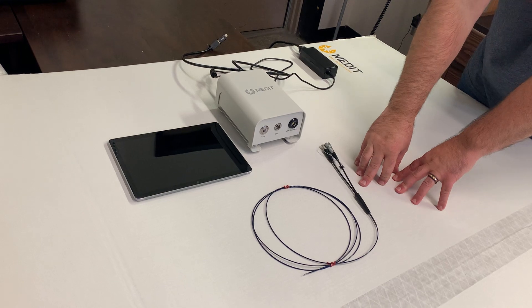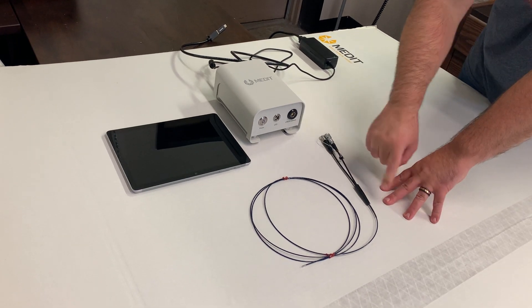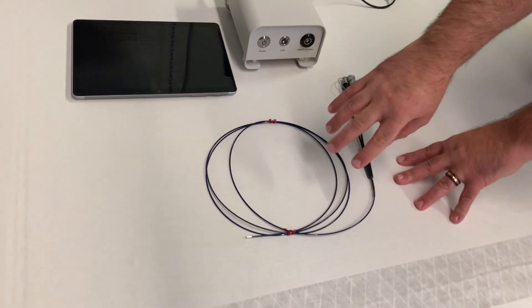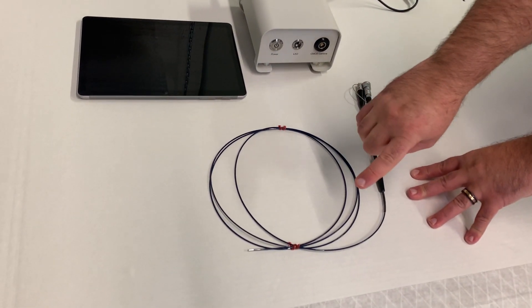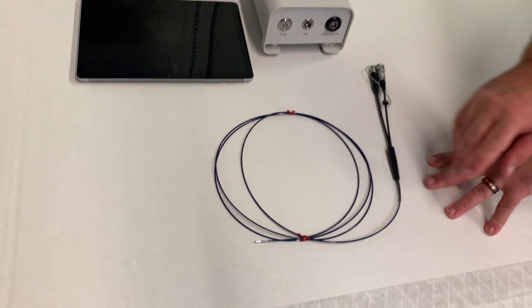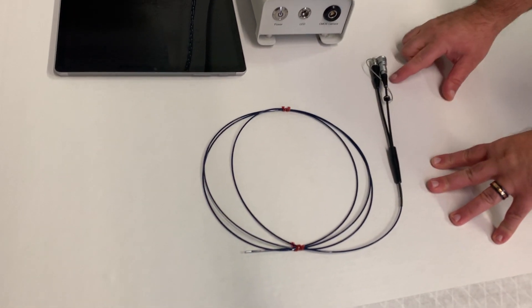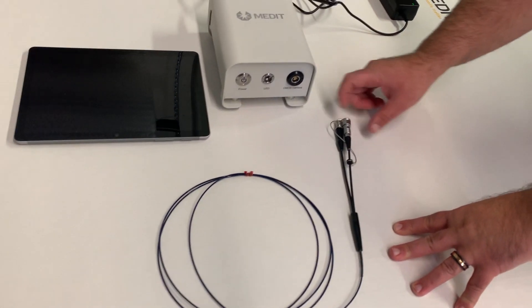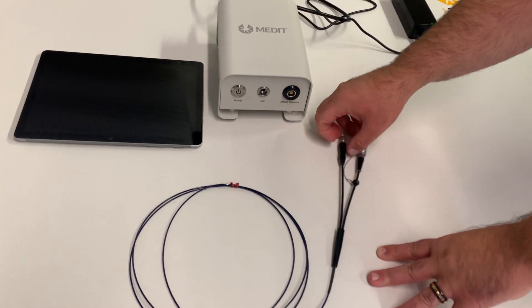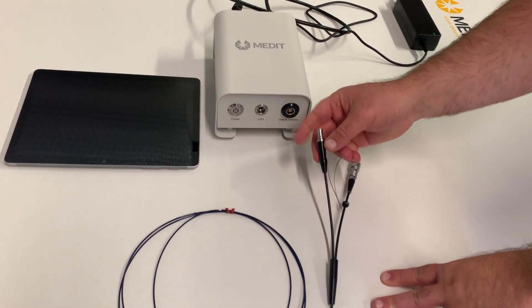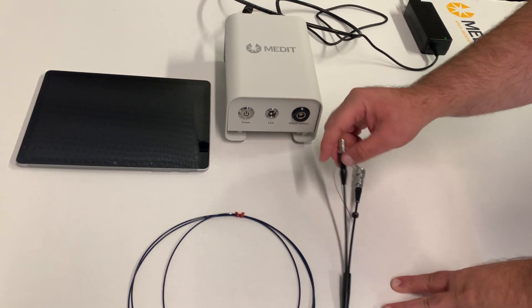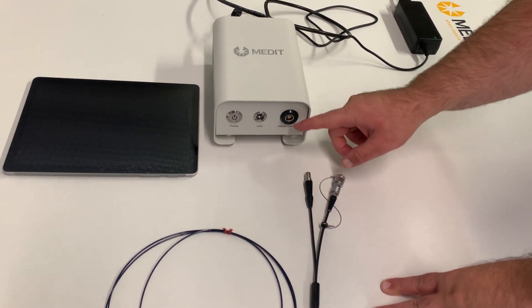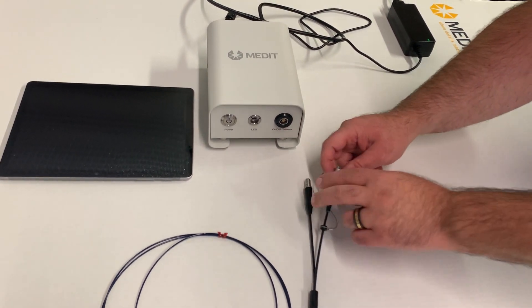Basically your video probe is right here. This is our demo 1.7 millimeter unit. You can see it's got a little bit of a tip on it and then a bifurcated cable. So on here you've got your light cable that'll transfer the LED light out of the tip and you've got your CMOS video connection cable.